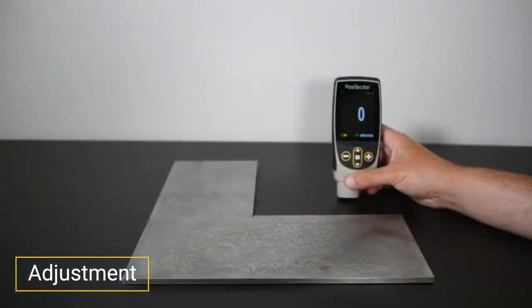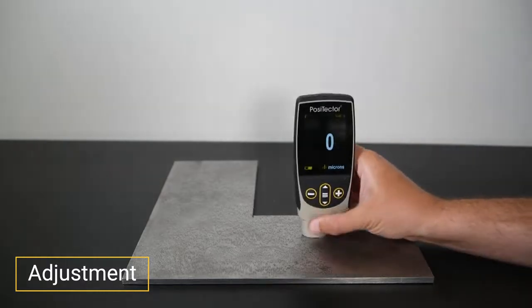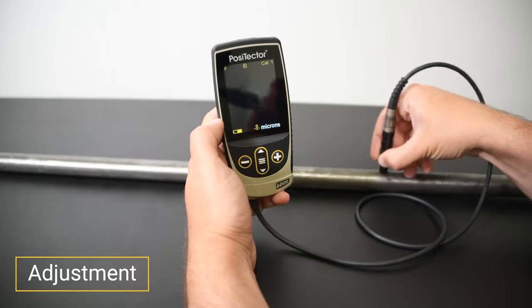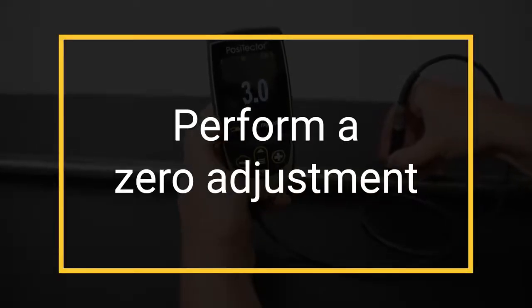Check zero on the uncoated substrate. If the instrument measures within tolerance at zero, the instrument is measuring accurately. If not, typically due to substrate mass, composition, or geometry, simply perform a zero adjustment.